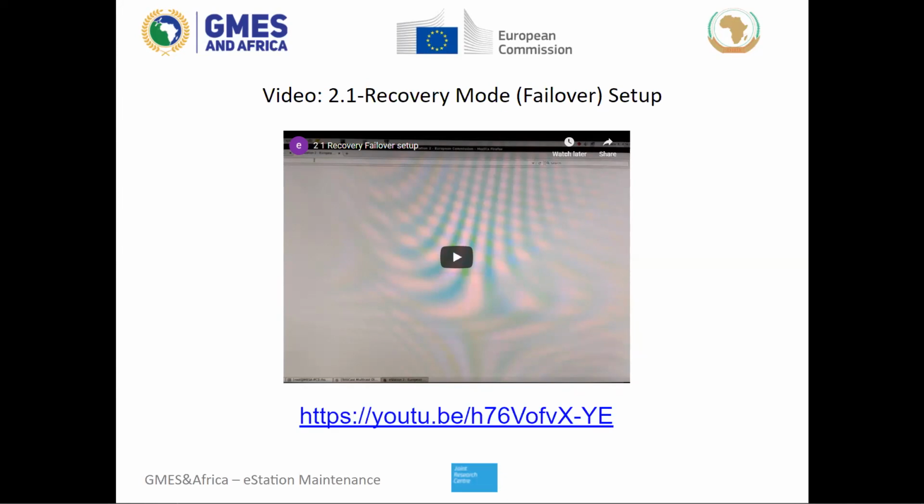But at the same time, we wanted to display here in this session all the possible operations you have to do. And then, according to the real situation you have to face, some of them are going to be necessary or not. For instance, if you have the 3 computers completely new or completely broken, you cannot enter the recovery mode because PC3 is not working. And this is also not possible if you have 2 computers broken, because the recovery or failover mode still requires at least two computers running, exactly.